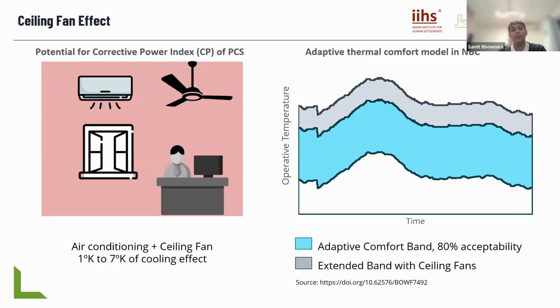Of course, we are talking about active HVAC systems today, but before you get to this stage, you should have optimized your building. A very well designed envelope is the best HVAC equipment you can have, and you can't do anything better than that. Equipment efficiencies in this industry may vary by about 4 or 5%, but almost 50% of the impact on cooling load is controlled by passive design, and that should have happened before you reach the stage of active HVAC design.